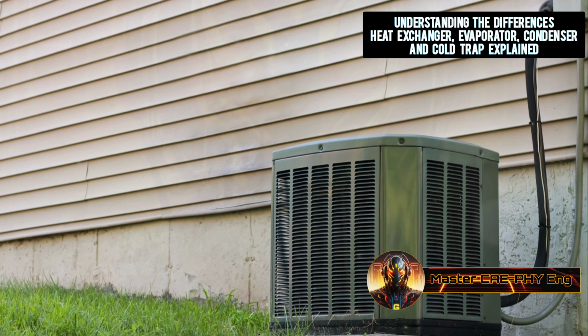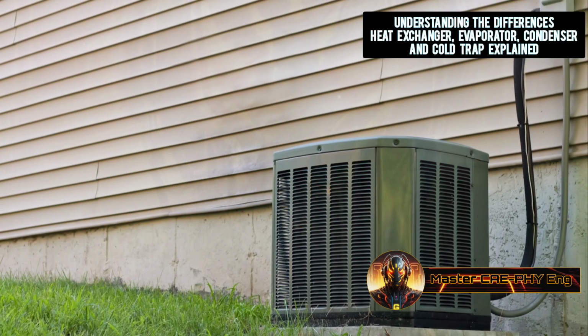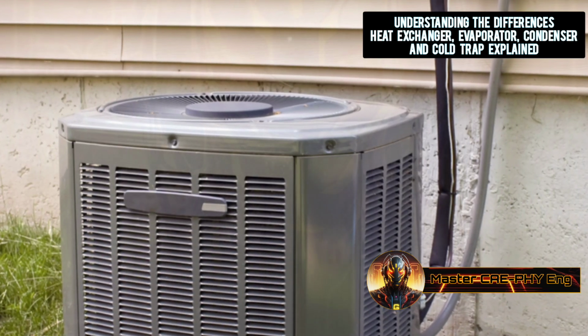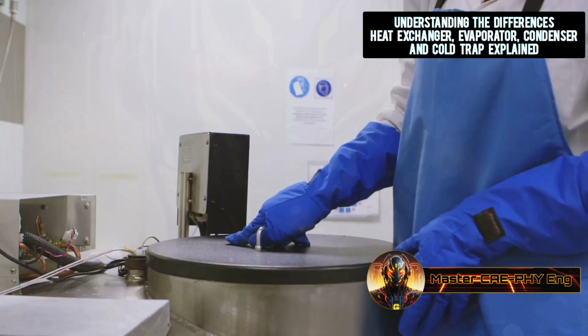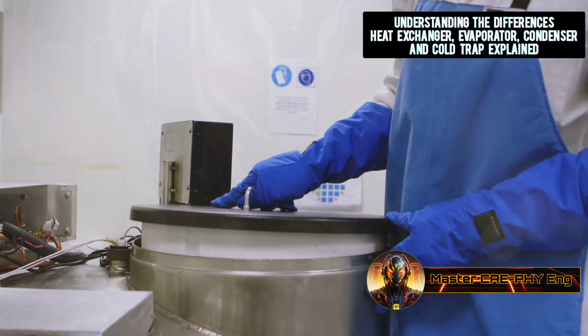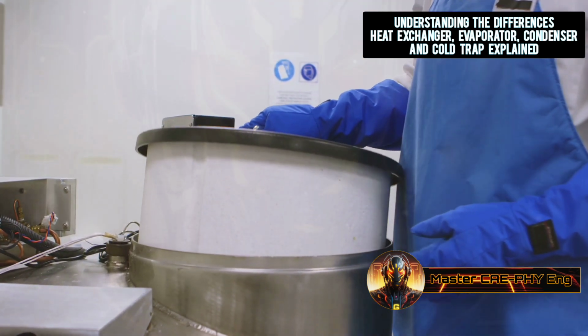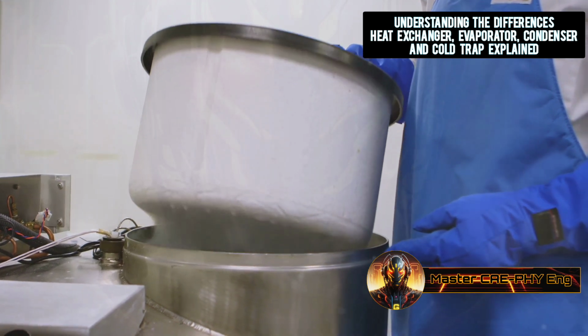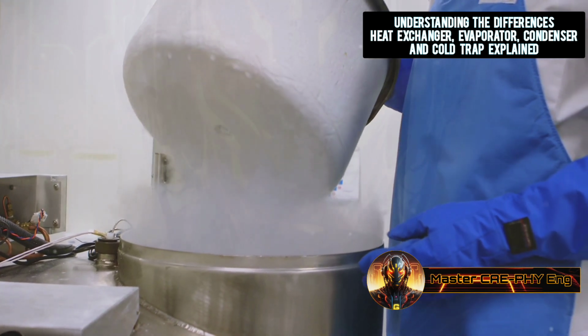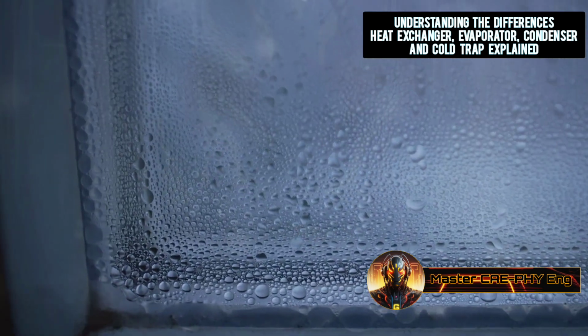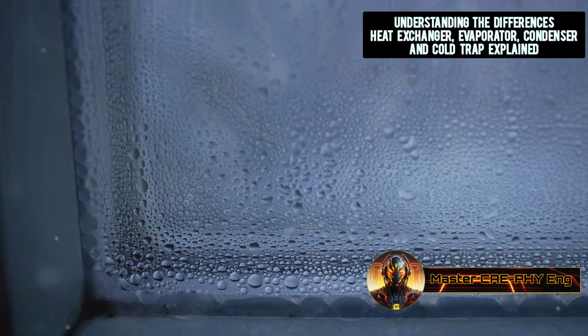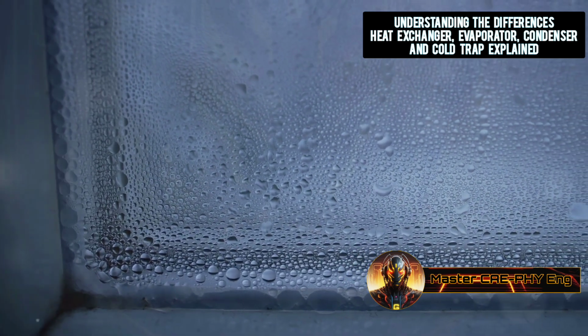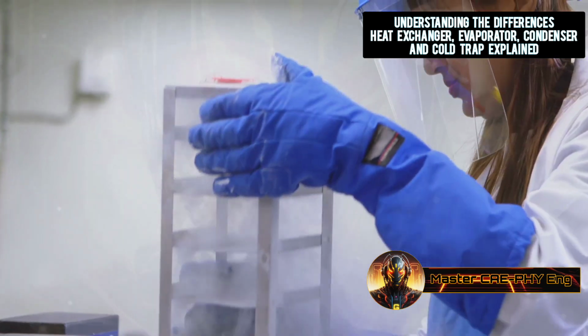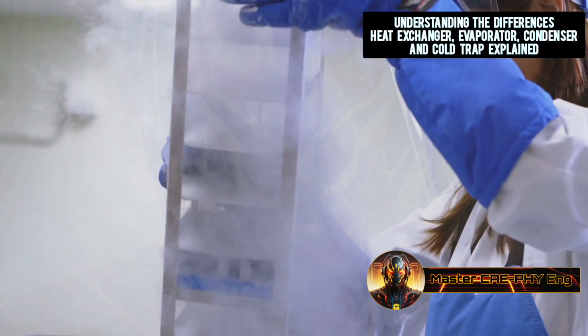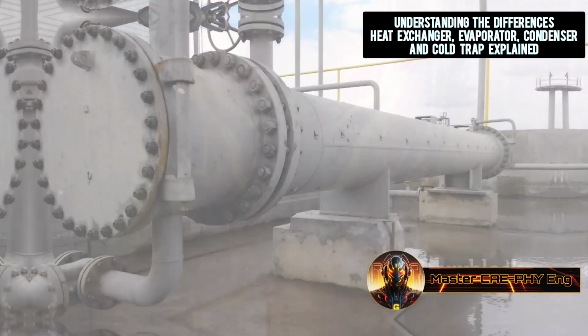Condensers are primarily designed to change the state of a refrigerant from vapor to liquid as part of a continuous cycle. Cold traps, on the other hand, are specifically designed to capture and remove unwanted substances from a vacuum system, preventing contamination. Think of it this way: a condenser is like a water cycle, constantly changing water between liquid and vapor. A cold trap is like a net, catching and holding on to impurities.